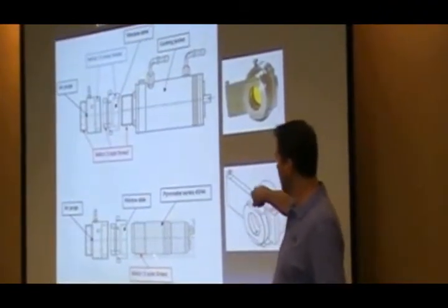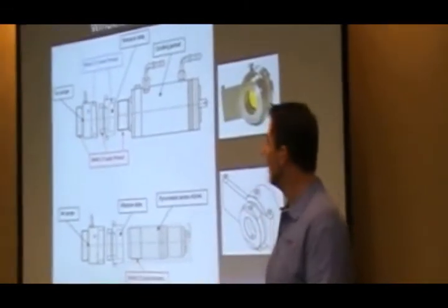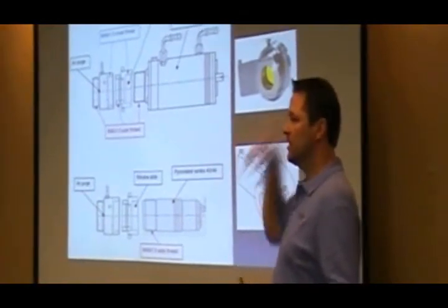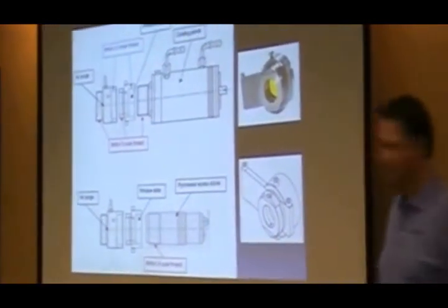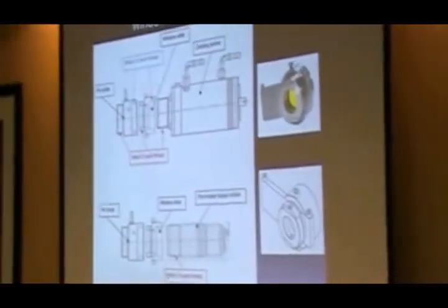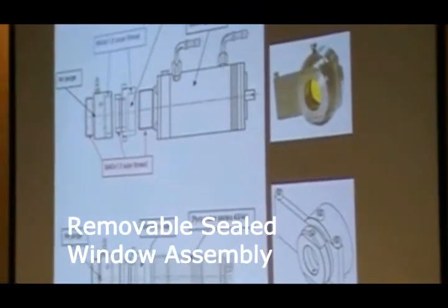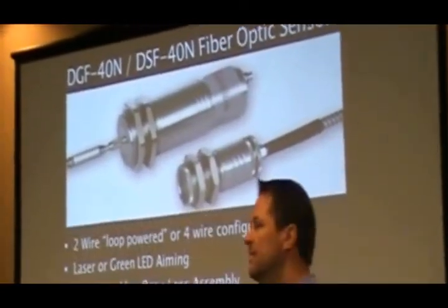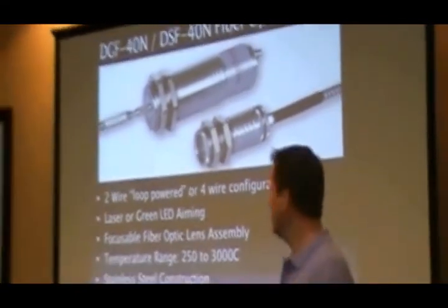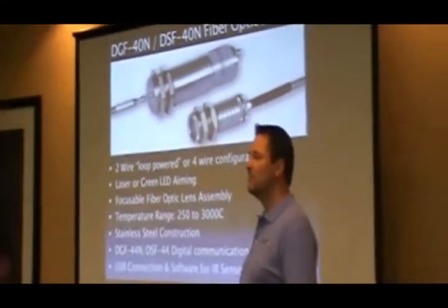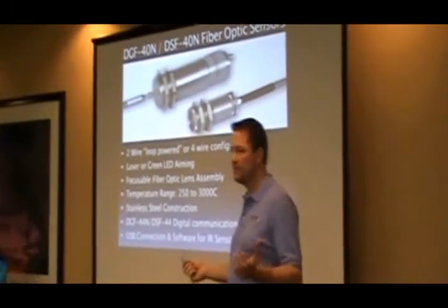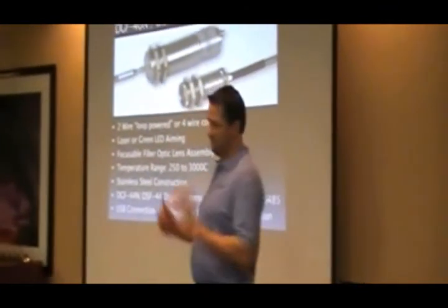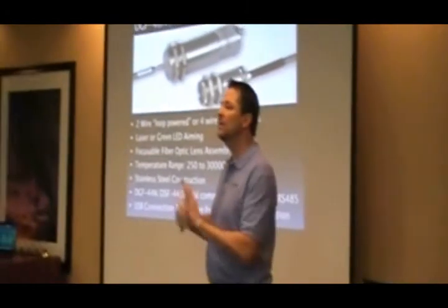Is that window replaceable? Yes it is. It'll have a retaining ring, unscrew the retaining ring and take it out. So this offers that slide window assembly. Who uses the slide window? In many dirty environments, even steel industries, they'll use it because inherently what happens is people shut off the air purge. That happens no matter where you go, and then the lens gets dirty. So here at least you can shut off the air purge, the window gets dirty, and you can clean the window.